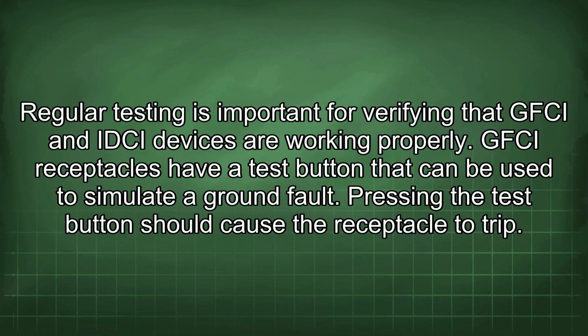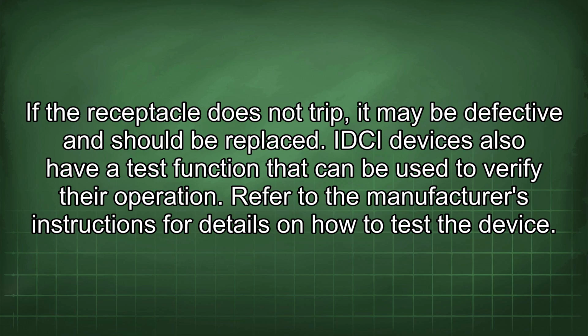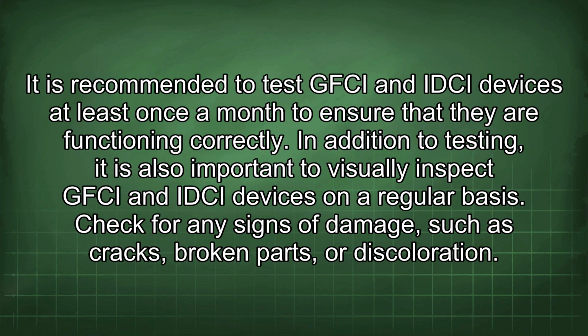Regular testing is important for verifying that GFCI and IDCI devices are working properly. GFCI receptacles have a test button that can be used to simulate a ground fault. Pressing the test button should cause the receptacle to trip. If the receptacle does not trip, it may be defective and should be replaced. IDCI devices also have a test function that can be used to verify their operation. Refer to the manufacturer's instructions for details on how to test the device. It is recommended to test GFCI and IDCI devices at least once a month to ensure that they are functioning correctly.